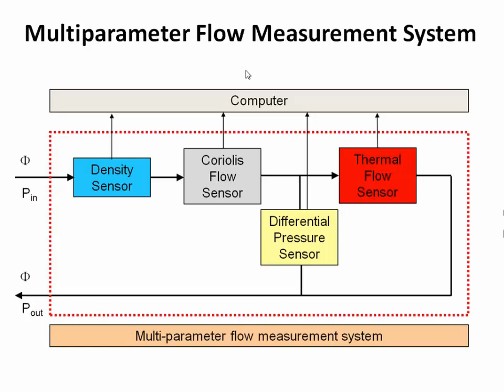While flowing, we measure at the same time the density with a density sensor, the mass flow with a Coriolis flow sensor, the differential pressure over the line with a differential pressure sensor, and again the mass flow with a thermal flow sensor. And this we can put into a model, and with this model we can determine the gas composition. So how do we do it?